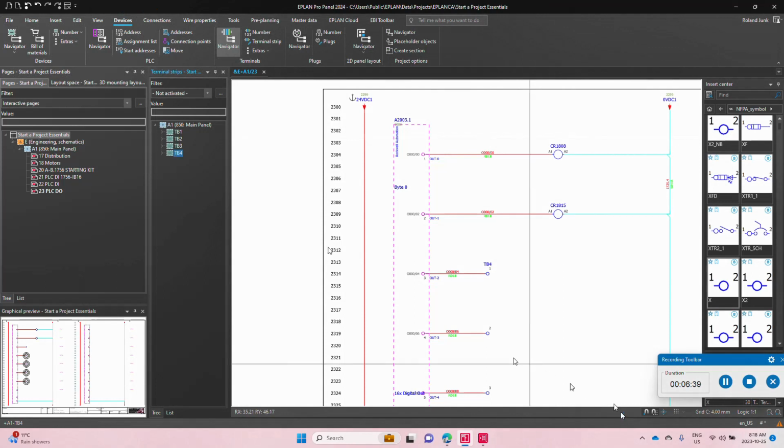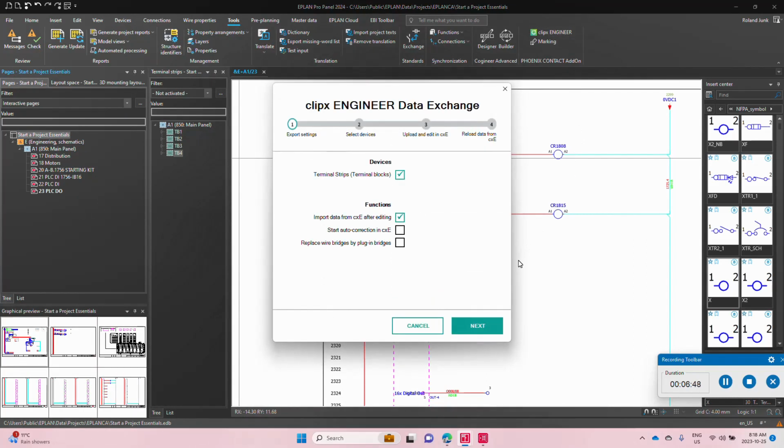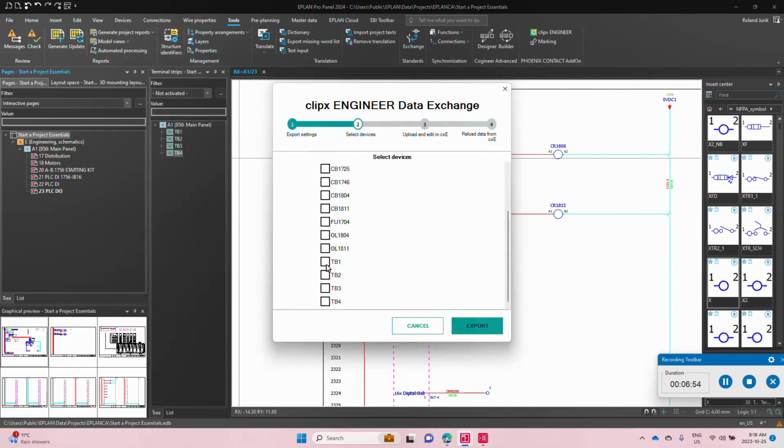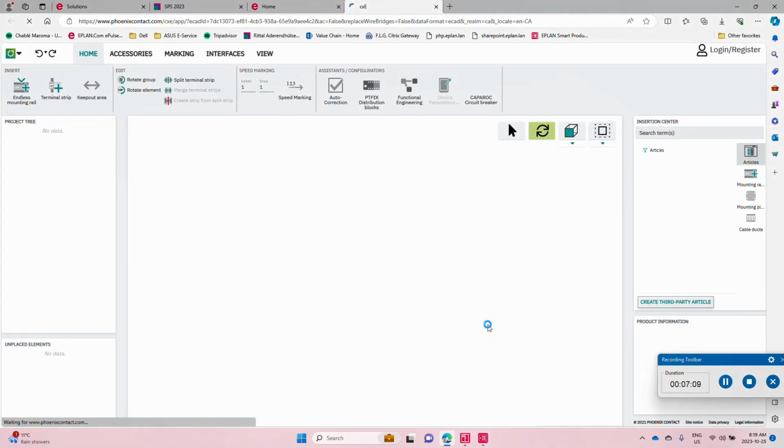terminals on this TB4. But what I'm missing are special isolating plates and other items, which with clipx ENGINEER, so this is a tool that we worked out together with Phoenix Contact, where you can very quickly pick your terminals and you can have them corrected, right? So remember, every terminal is open on one side, and it requires an isolating plate to actually be absolutely finger safe.